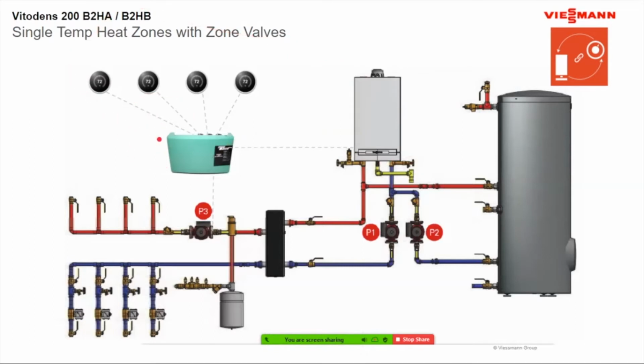You can have one doing a fixed set point, and you can have one group doing modulation to the outdoor temperature. So you can do 3 different temperatures out of this boiler and a fixed set point. The neat thing with the 200, I recommend doing outdoor modulation, even if you're doing hydrocoils or heat coils or things to that nature, because you can put a minimum and a maximum on our heating curves through coding. So it won't allow it to drop down. Say you're doing a heating curve and you don't want to go below, say, 140. You can say, okay, I don't want to go below 140, I don't want to go over 160, whatever. So you can still modulate to the outdoor temperature, but you're not going to go down so low that it's going to blow cold air.